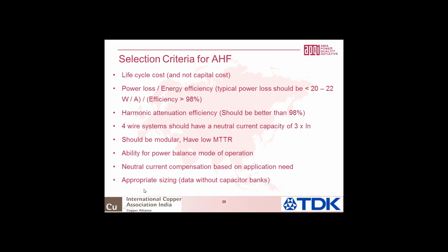And the most important is the sizing, the last line, where you should have harmonic data without capacitor banks. Because when you have simple capacitor banks, it will be very scary. You can have a 40% distortion, which doesn't mean that you end up buying a very big active filter. You remove the capacitor bank, see what is the distortion, buy an active filter, and the rest of the reactive power compensation could be done with more cost-effective and efficient devices like detuned capacitor banks.